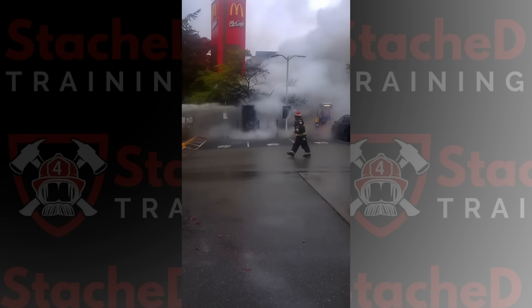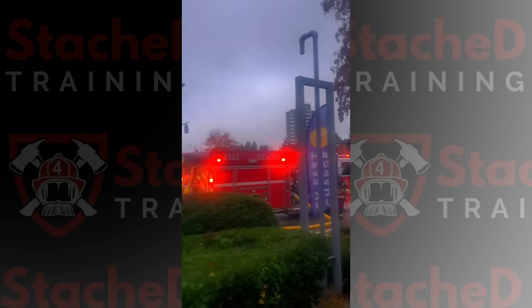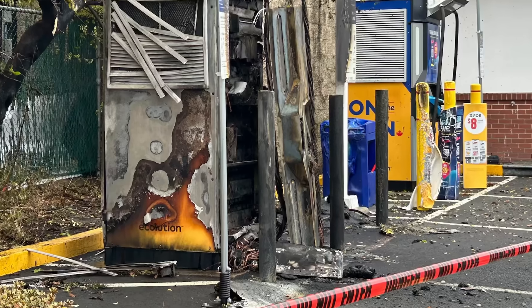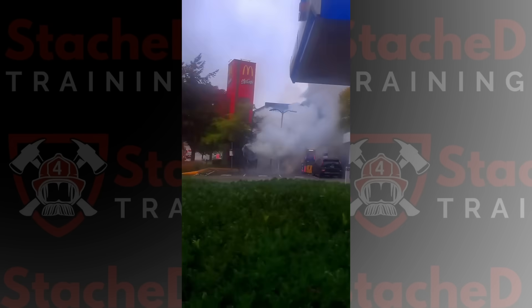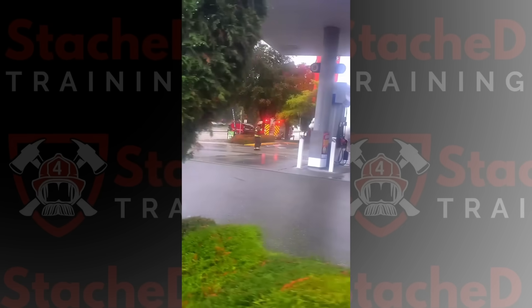Surprisingly, this is one of the first examples of this type of system I've seen catching fire. Fire officials haven't released details about the point of origin or the specific charger, but details online confirm this charger was using a battery buffer design. Looking at the aftermath, the components down low in the cabinet appear to be the batteries themselves. After the fire is mostly out, it does appear that there are still batteries inside off-gassing — though the video clip is too short to get a good sense of what's going on.